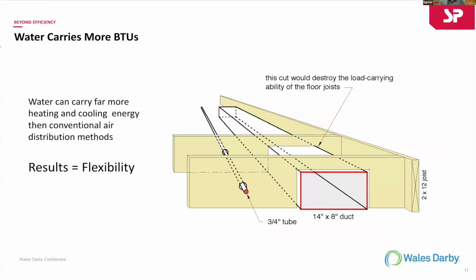So like I said, look at the difference. I can run all these BTUs through a 3/4 inch pipe, as opposed to, to match it, I've got to use a 14 by 8 inch piece of ductwork to move that amount of air. So that alone, again, is space saving and things like that. It's just the convenience of running hydronic heating. It is just the most flexible way to heat a home.